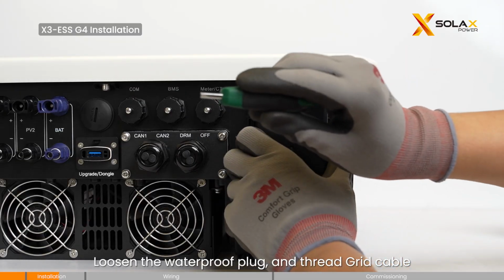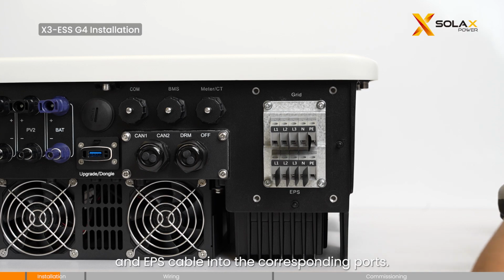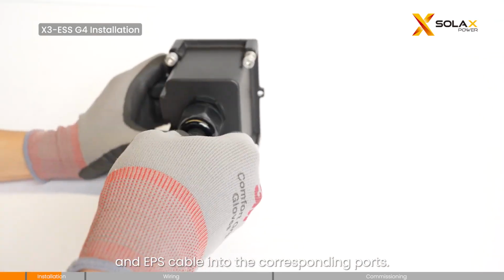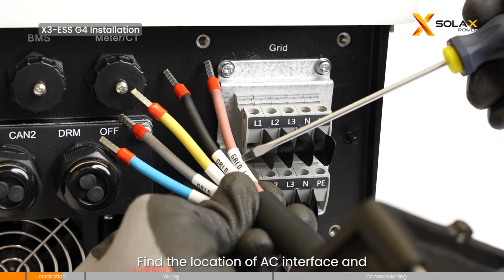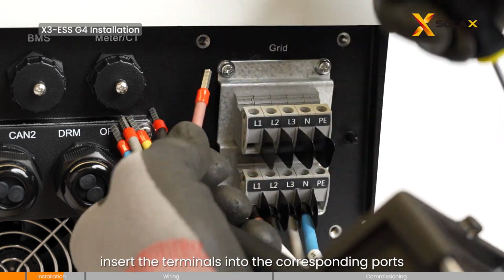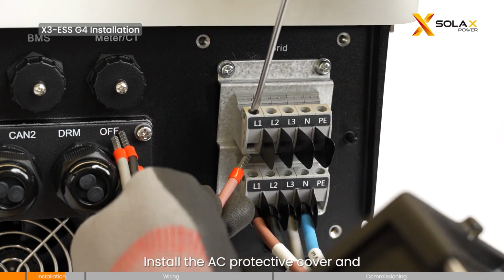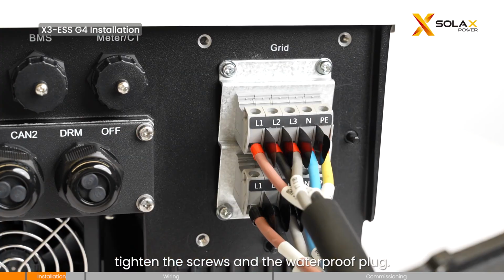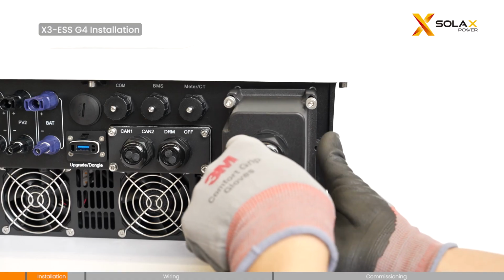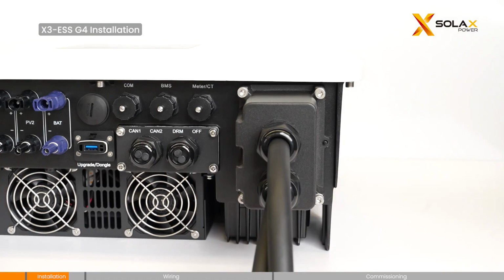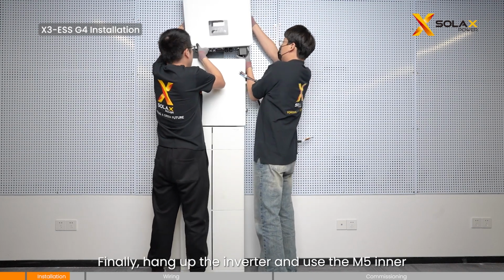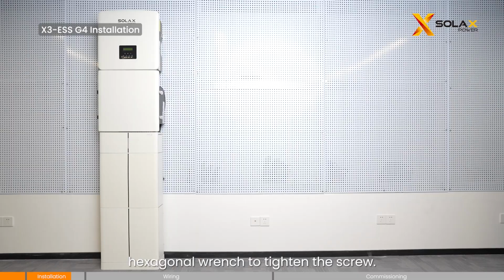Loosen the waterproof plug and thread grid cable and EPS cable into the corresponding ports. Find the location of AC interface and insert the terminals into the corresponding ports. Install the AC protective cover and tighten the screws and the waterproof plug. Finally, hang up the inverter and use the M5 inner hexagonal wrench to tighten the screw. And X3-ESS G4 installation is finished.